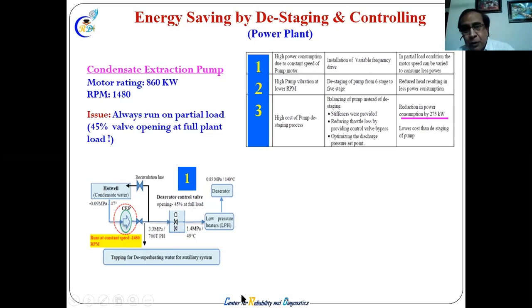So VFD is not the solution everywhere. There may be many other problems, electro discharge machining of the bearing, many other issues. So there is a problem in the vibration of this pump. When they lower the speed, it matches the resonance frequency, meaning the natural frequency of the structure. Okay, every structure and piping will have a natural frequency. The suction side is such, whatever it may be. So they changed again to a different stage pump, from 6 stage to 5 stage pump. And the 5 stage pump also has a problem.